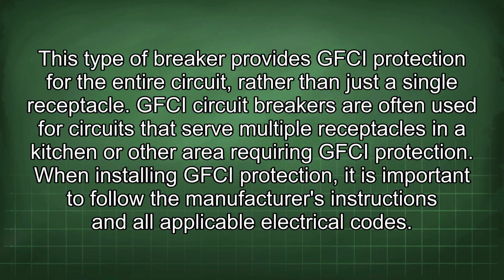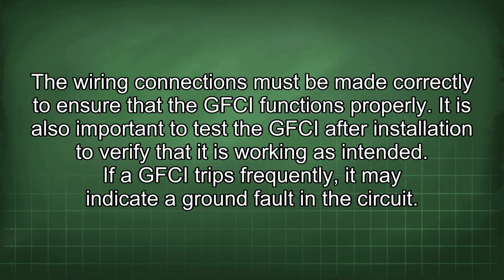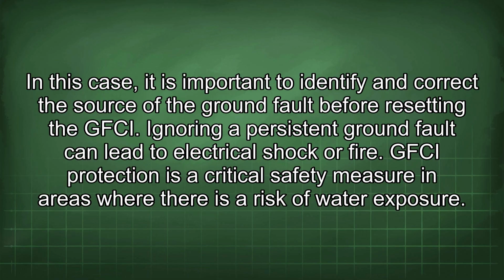GFCI circuit breakers are often used for circuits that serve multiple receptacles in a kitchen or other area requiring GFCI protection. When installing GFCI protection, it is important to follow the manufacturer's instructions and all applicable electrical codes. The wiring connections must be made correctly to ensure that the GFCI functions properly. It is also important to test the GFCI after installation to verify that it is working as intended. If a GFCI trips frequently, it may indicate a ground fault in the circuit. In this case, it is important to identify and correct the source of the ground fault before resetting the GFCI. Ignoring a persistent ground fault can lead to electrical shock or fire.